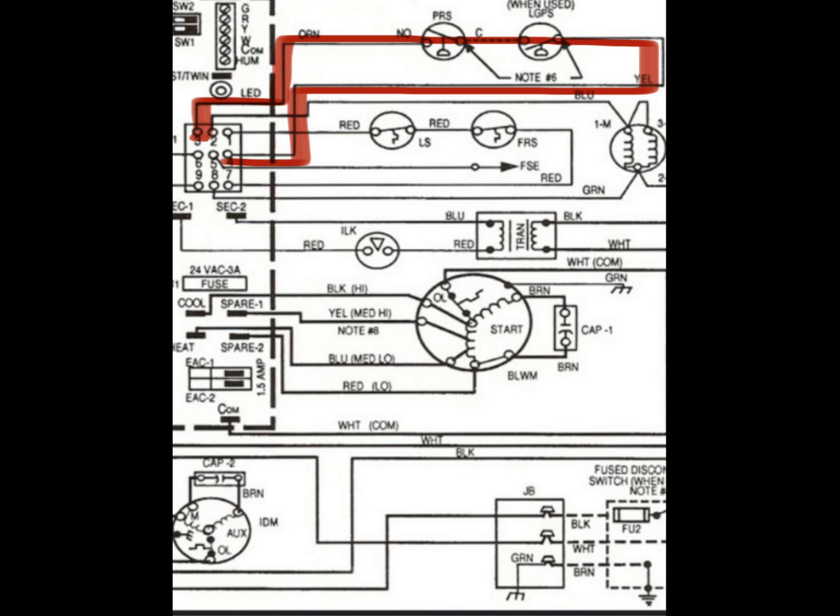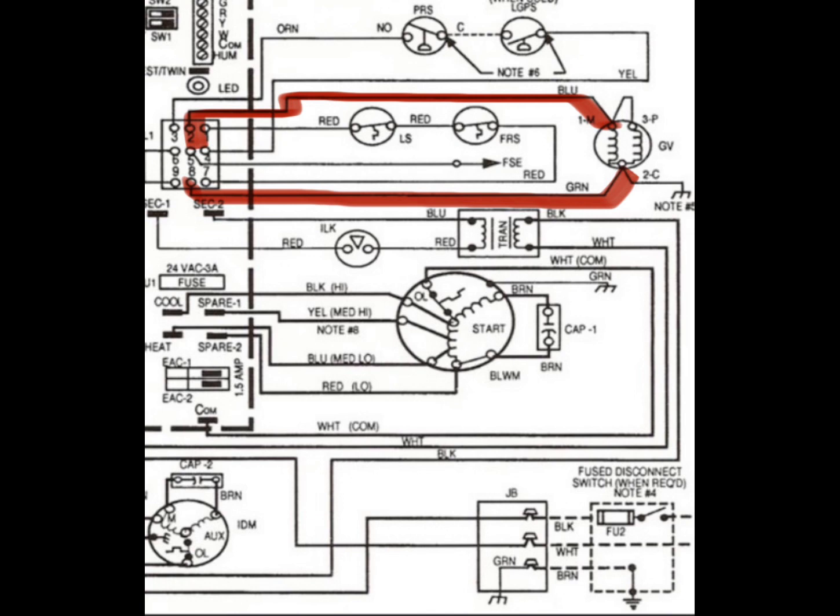So the very first thing in this furnace's sequence: thermostat calls for heat, the W pin lines up, the induced draft motor, L1, that first plug right there lights up with line voltage. Induced draft motor comes on, creates the suction. The suction is read by what we're looking at on our screen right now, which is this normally open, normally closed pressure switch. The switch closes, this passes voltage all the way back into this pin right here, which we see is a number 4.